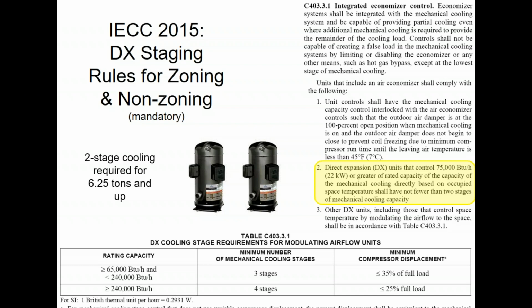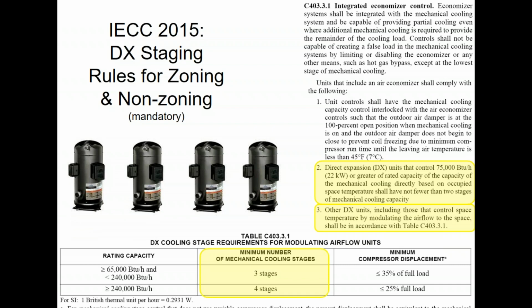So keep that in mind: if you have those size units, you're going to need to have multiple stages. Then, more interestingly, from the controls guide perspective, number 3, other DX units, including those that control space temperature by modulating airflow to the space, shall be per the table below. Modulating airflow to the space to control space temperature, that would be a VAV system, or a VVT system, or some other type of air-based, damper-based zoning system. The thermostat controls the airflow damper, right? Space temperature to control airflow, or rather using airflow to control space temperature.